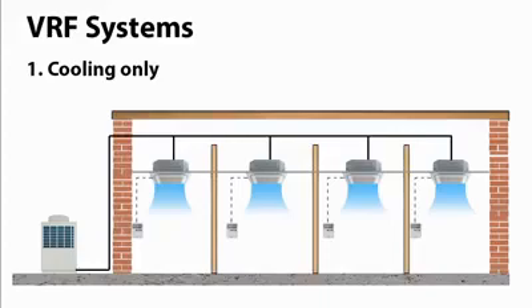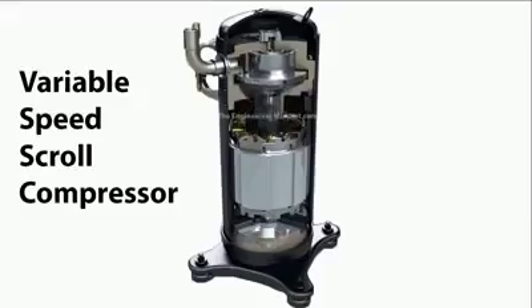a single branch, being the flow and return, and they also have much better control, enabling them to match the exact cooling load of the entire building. As previously stated, these systems use a variable frequency drive to control the speed of the scroll compressor, and that's allowing the entire system to match the exact cooling load of the building.